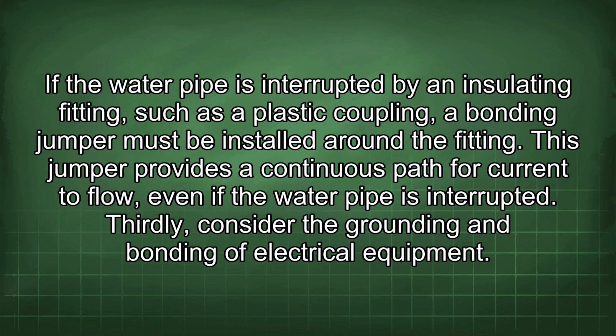If the water pipe is interrupted by an insulating fitting, such as a plastic coupling, a bonding jumper must be installed around the fitting. This jumper provides a continuous path for current to flow, even if the water pipe is interrupted. Thirdly, consider the grounding and bonding of electrical equipment.